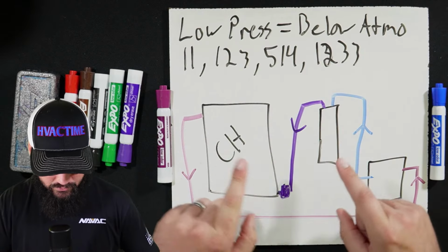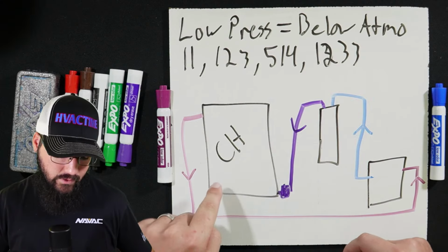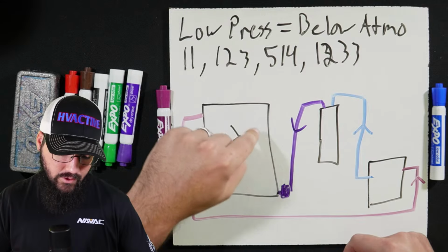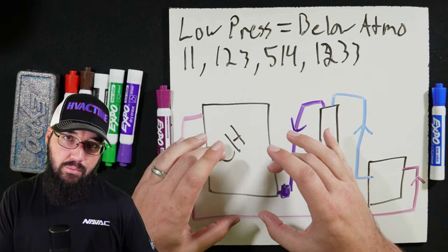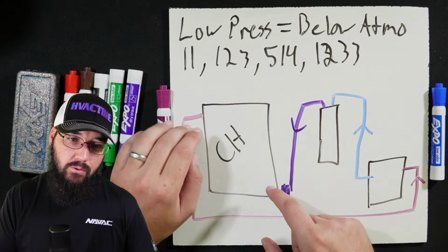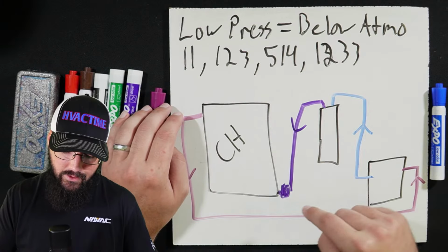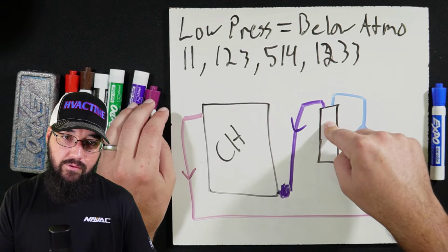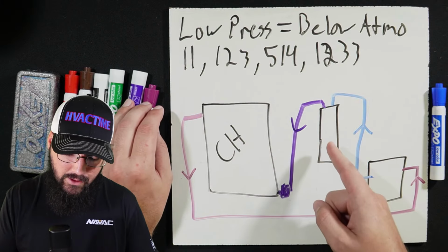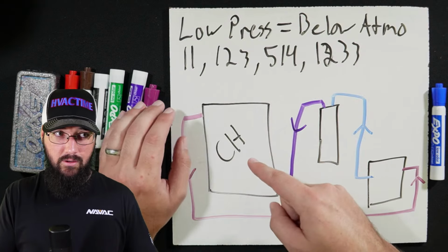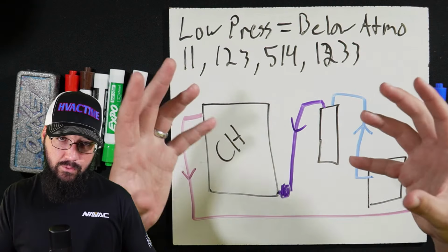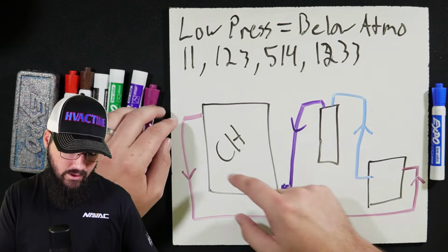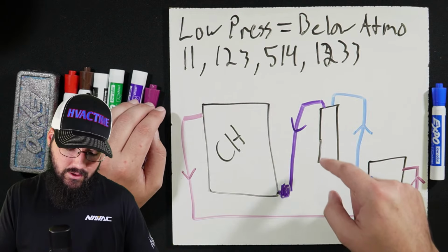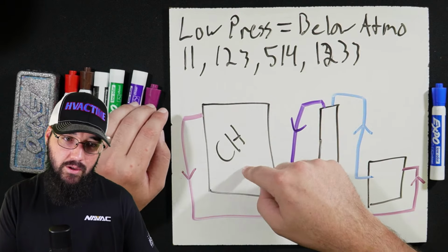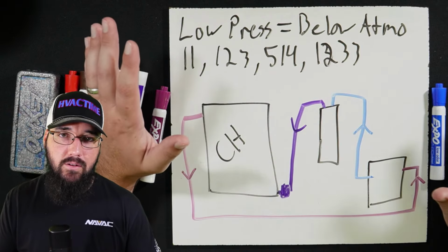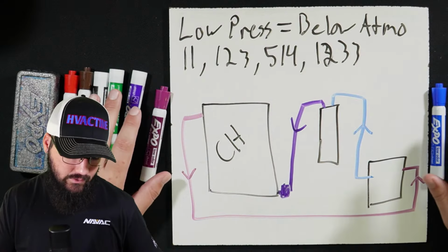And so what's happening is twofold. One, we're drawing vapor off of the chiller. Drawing that vapor off lowers the pressure in the chiller, which naturally makes the liquid refrigerant want to siphon. But we're then pushing that vapor into the cylinder itself. Pushing that vapor into the cylinder is going to then naturally want to push that liquid refrigerant out of the cylinder. And that's where the whole concept of push and pull comes from. We're pulling with this line, pulling off of the machine, and we're pushing with the vapor in the tank into the machine. And the speed of this compared to other methods is just crazy.